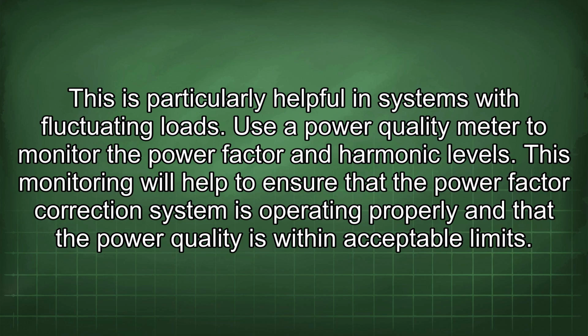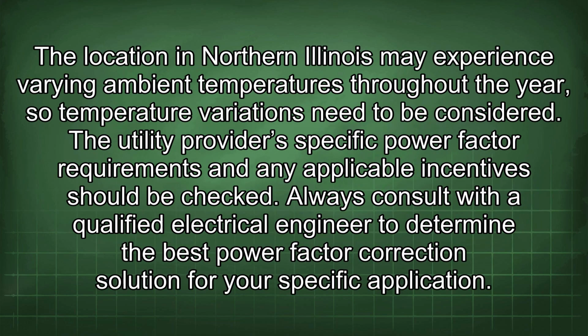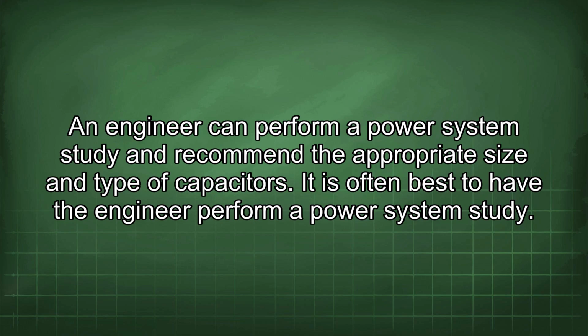Use a power quality meter to monitor the power factor and harmonic levels. This monitoring will help to ensure that the power factor correction system is operating properly and that the power quality is within acceptable limits. The location in northern Illinois may experience varying ambient temperatures throughout the year, so temperature variations need to be considered. The utility provider's specific power factor requirements and any applicable incentives should be checked. Always consult with a qualified electrical engineer to determine the best power factor correction solution for your specific application. An engineer can perform a power system study and recommend the appropriate size and type of capacitors. It is often best to have the engineer perform a power system study.